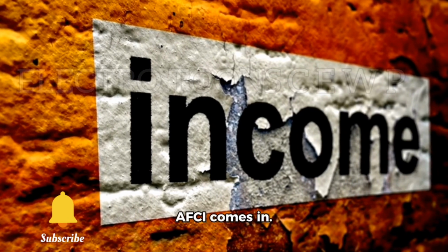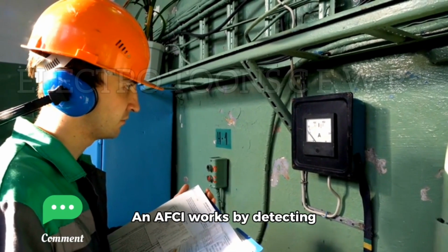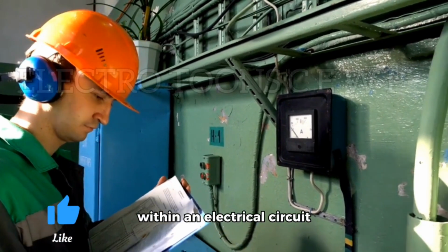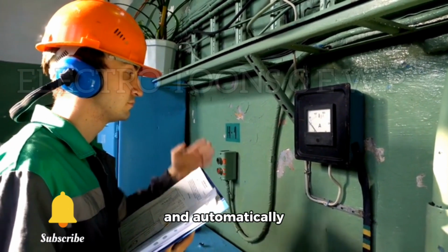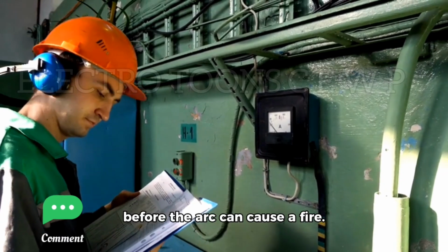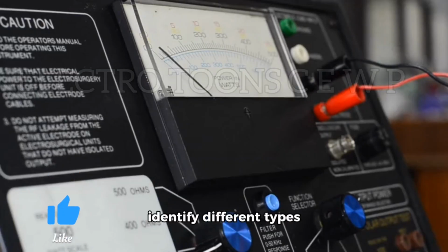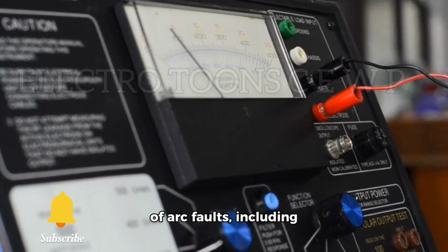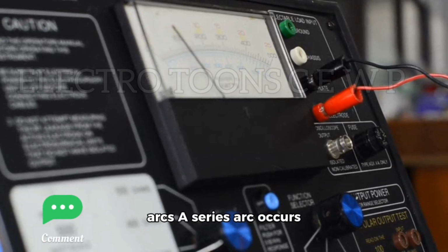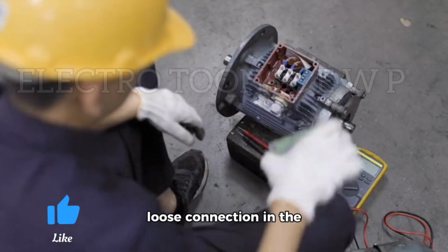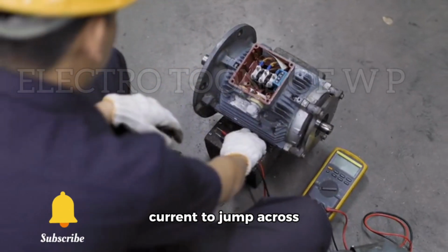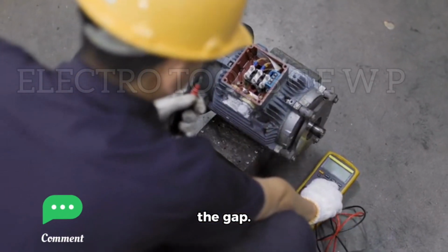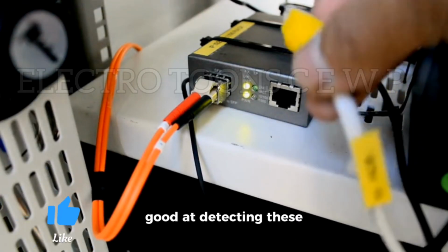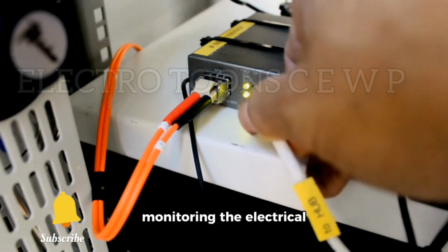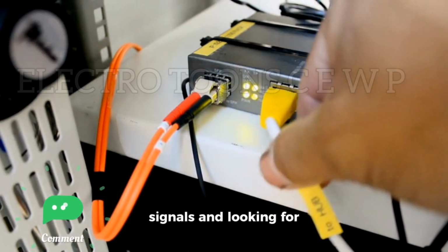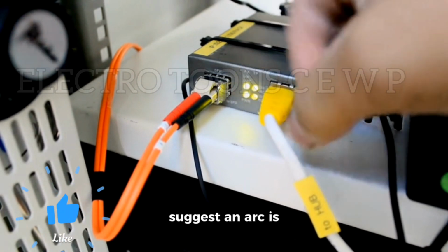This is where an AFCI comes in. An AFCI works by detecting the presence of arc faults within an electrical circuit and automatically disconnecting the power before the arc can cause a fire. The device is designed to identify different types of arc faults, including series arcs and parallel arcs. A series arc occurs when there is a break or loose connection in the circuit, causing the current to jump across the gap. AFCIs are particularly good at detecting these types of faults by monitoring the electrical signals and looking for irregularities that suggest an arc is occurring.